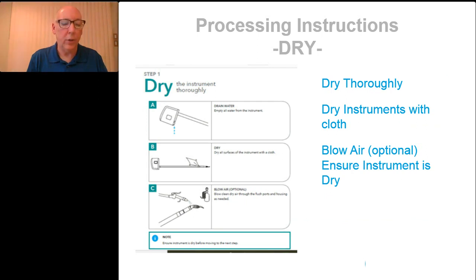Drying instruments with a cloth will certainly meet one of the principles of drying, using a towel, no doubt about it, but what about the lumens and the internal components? Ensuring the instrument is dry, certainly you can see the exterior is dry, but what about the interior? The shaft of the device, the lumens, the base of the device with its internal components. So just as we previously mentioned, in order for devices to be dry at the end of the sterilization process, they need to be dry at the beginning of the process.